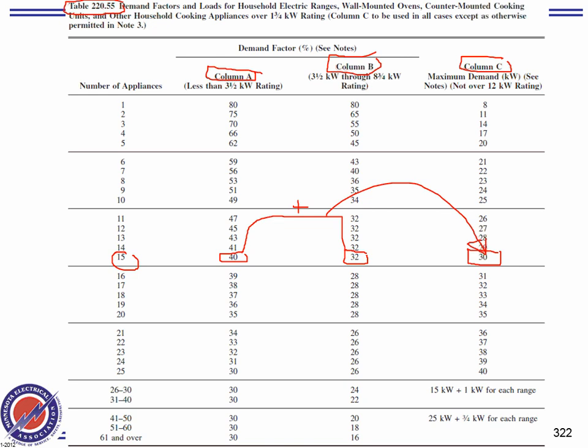What happens if you get above 12? Then you have to go to note number 1. Can you guys see note number 1 on the table? It says equal sizes ranges with nameplate greater than 12 kW. If they're all the same size, then you use, say, more than 12. So all of them are 16. How far is 16 from 12? That's note number 1. Not number 2, Joe.